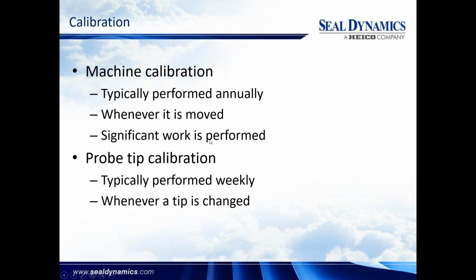Whenever you change a tip, and I don't mean whenever I have the machine change from one tip to the other. I mean, for example, something happens, you need to replace a tip, you want to design a new tip, put a shaft on it, you're going to change the geometry, dimensions, the features of this tip, you need to go and do a probe calibration.